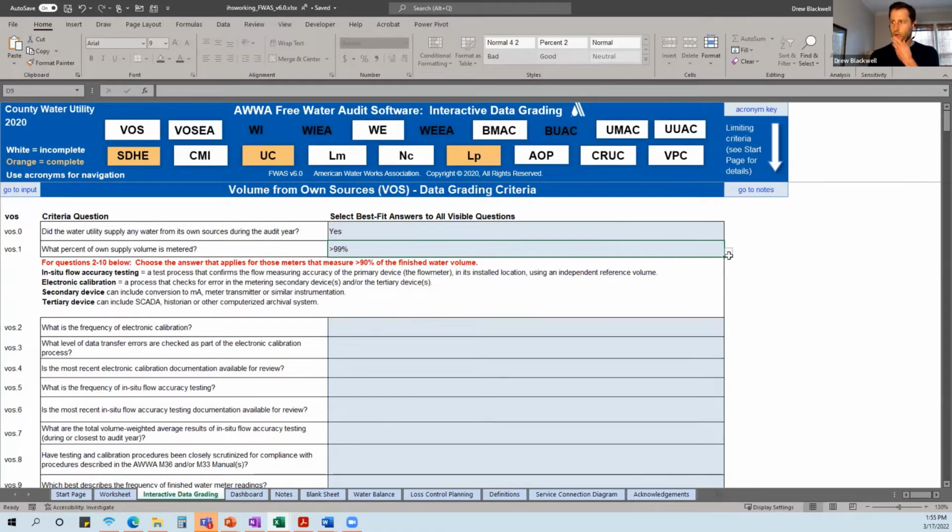All right. And so, Nicole, let's think about just how that might look for the one system where we drew that water audit boundary. We would still have 100% metered, but if you recall, 2 of those well meters in that system were registering the raw water, and then they fed into that treatment facility, and then there was no effluent meter registering the flow leaving that treatment facility. Ideally, if we had a meter at that treatment facility, that's what we would use.